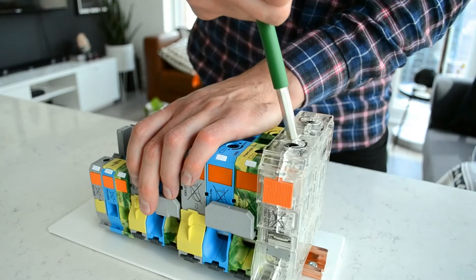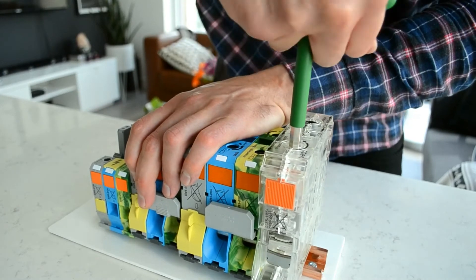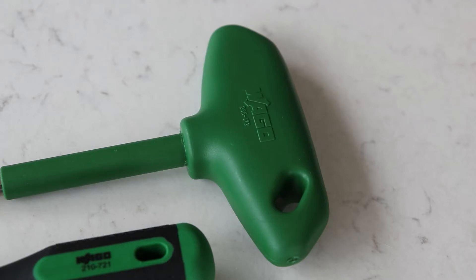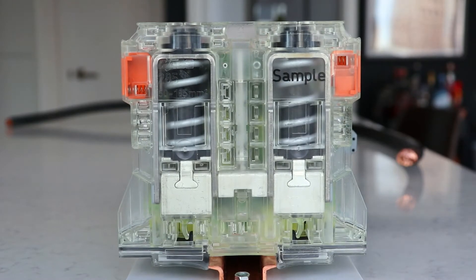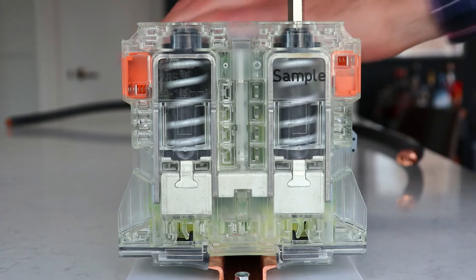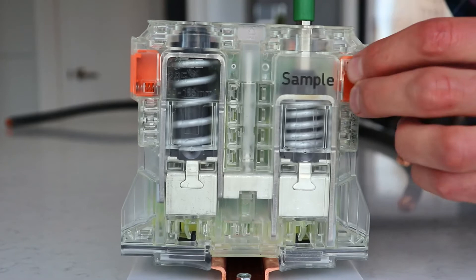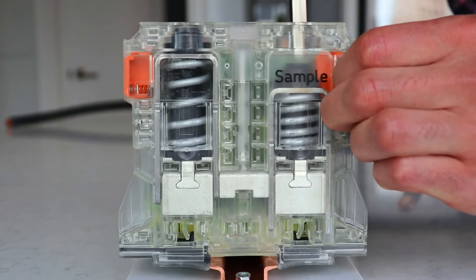This is the largest size terminal block WAGO offers and I am using a 350 kcmil cable to show it in action. The first step is to choose the correct tool for the block and twist it open. By pressing the button in on the front once you have reached a full turn, you will be able to lock the spring cage in the open position.